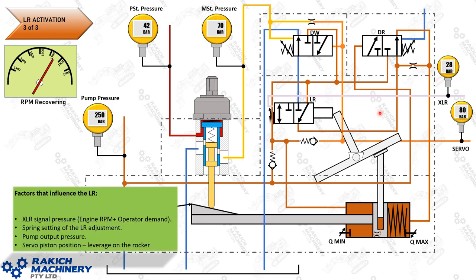To summarize: the factors that influence the LR are the XLR pressure input, which is controlled by engine RPM plus the operator demand; the spring setting of the LR valve; the pump outlet pressure acting on this rocker; and the servo piston position, which changes the leverage required to force the rocker — it takes a lot less pressure to push the rocker over when the piston is at full stroke than as it comes back. Very complicated, but it all contributes to the hyperbolic power curve that these pumps boast. This function has been made redundant on the 6060 model machines — on the 6060 you would find the LR adjustment is wound fully in and there is no XLR input anymore, so this whole function is disabled.